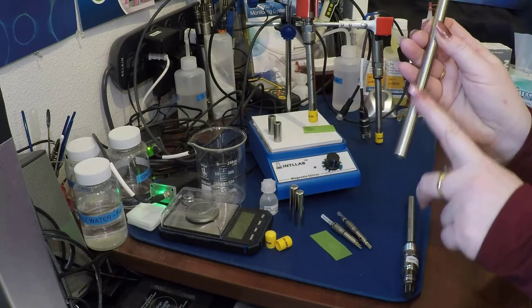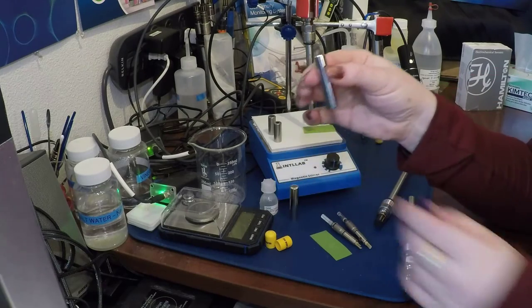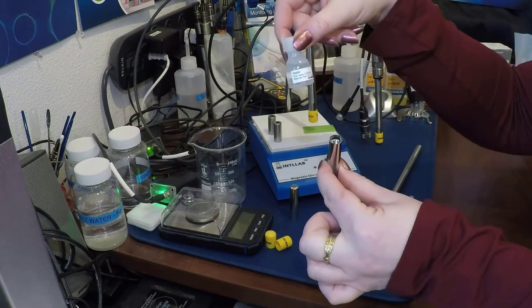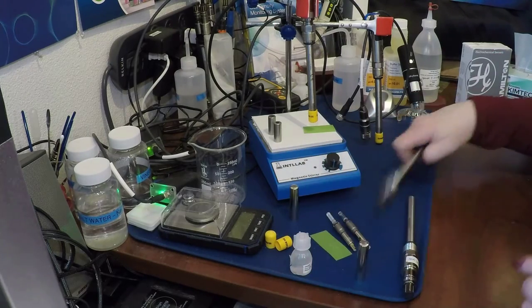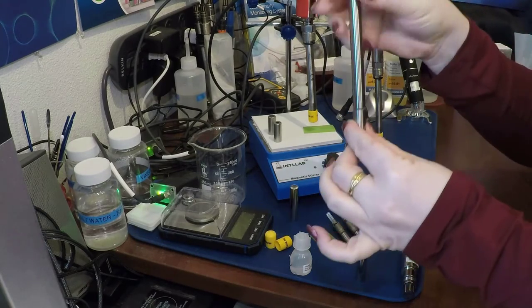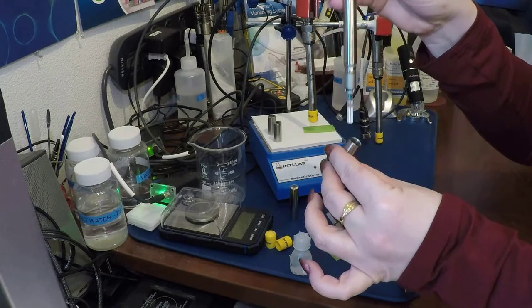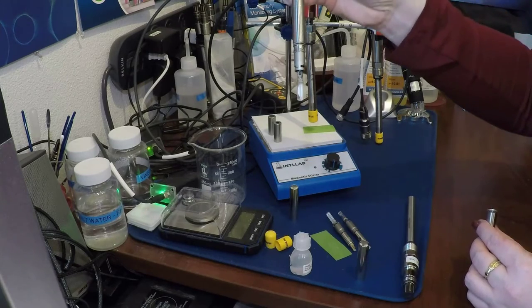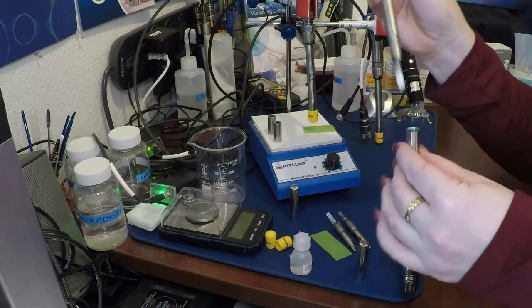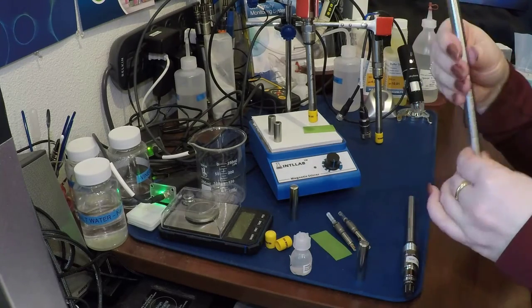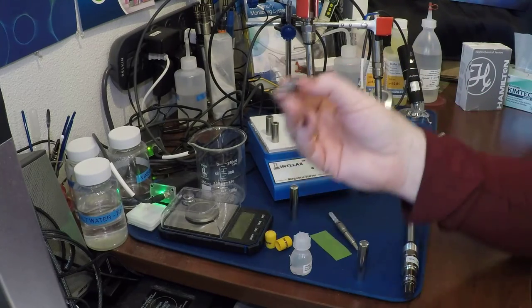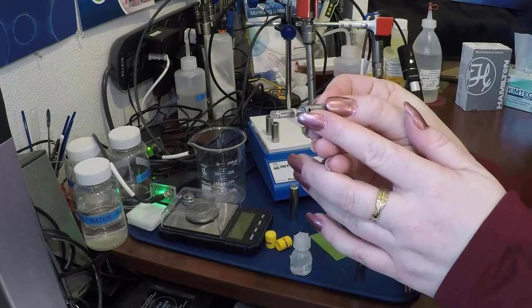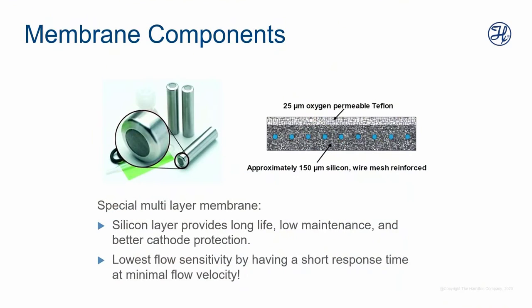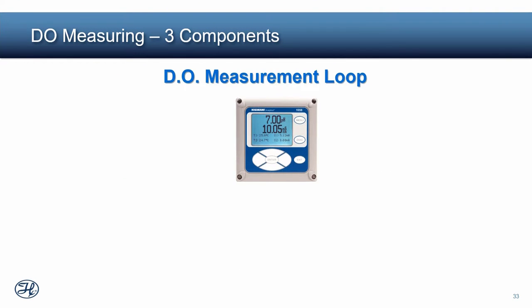Okay. Inside of this, if I was to take this apart, which I won't, if I take the probe off, there's liquid in here. This is the electrolyte. Okay. And inside of that, actually, go ahead. I'll take it apart. I'm just going to keep this upright though, because there is liquid. This is what it looks like inside. And this is what's called the anode cathode assembly. Okay. So, what does an anode cathode assembly look like? Well, conveniently, I happen to have one right here. There's tiny little wires on the end here. That's platinum. And this is the silver chloride. Okay. When you put all that together, you get a nanoamp signal out of the system.